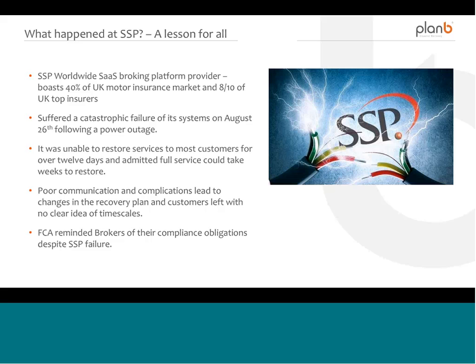In this event it didn't. The power went off to the data center, the batteries and the generators didn't kick in, and thousands of computers were dropped without proper shutdowns. That caused massive disruption within the storage network within the data center, with machines being physically damaged by the abrupt loss of power.